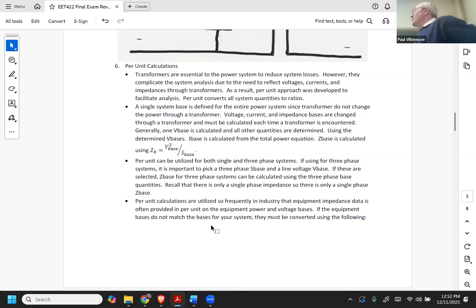If you purchase equipment, the industry standard is to give you the impedance on a per unit basis, based on the equipment ratings you purchased. So when you buy a transformer rated 100 MVA with certain voltage ratings, that's what the Z base and Z per unit are based on. Same thing with a generator: if you buy a 100 MVA, 13.8 kV generator, all the impedance data will be given in per unit based on that 100 MVA and 13.8 kV.